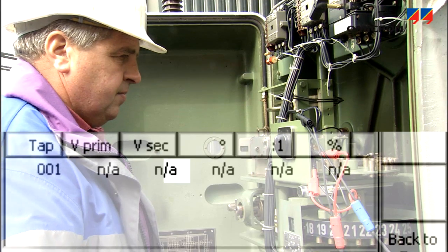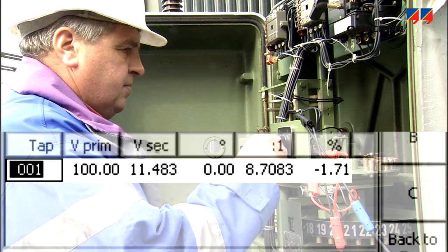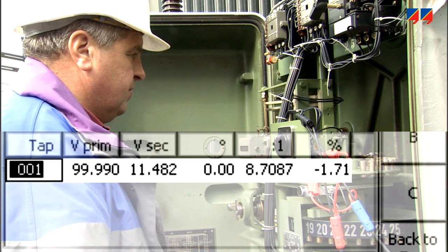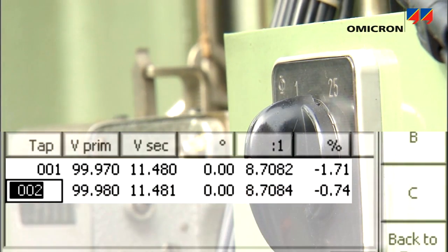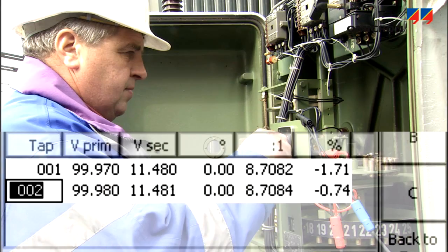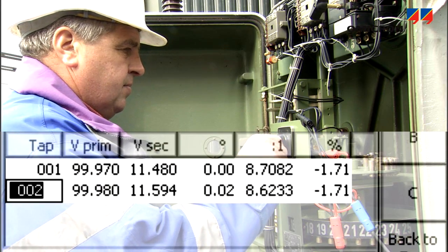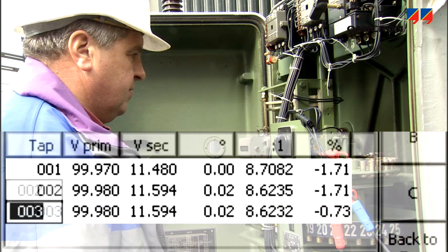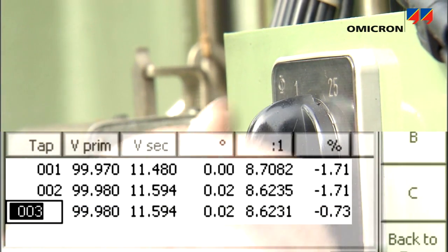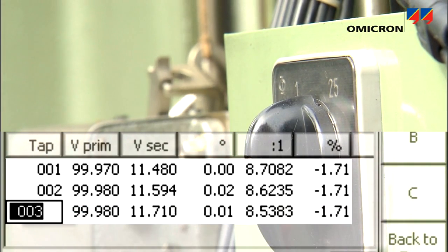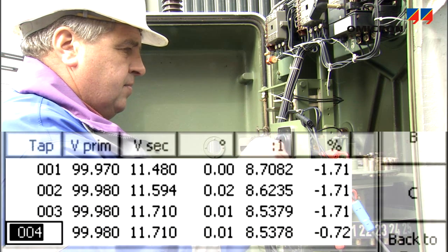For transformers with an on-load tap changer, the CPC simplifies the process by combining the measurements for all taps in one test run. Each time the user operates the tap changer, the ratio measurement is automatically performed for each tap.